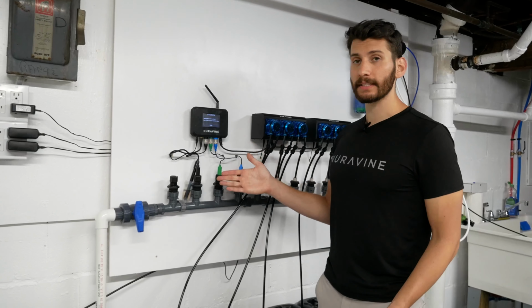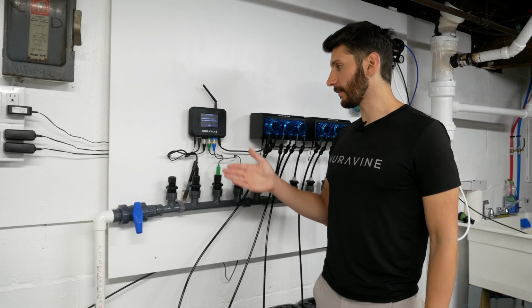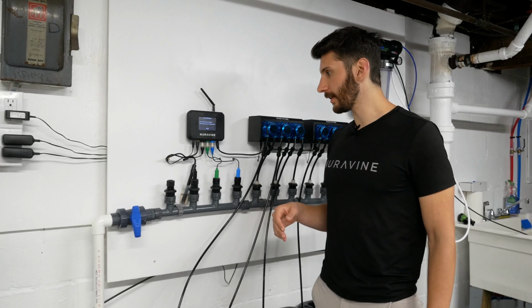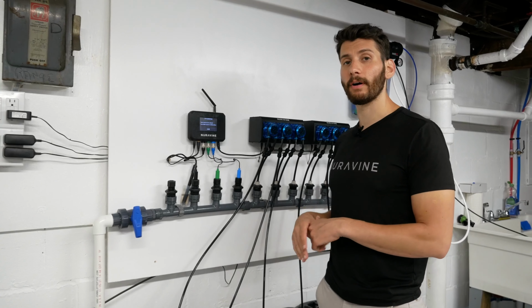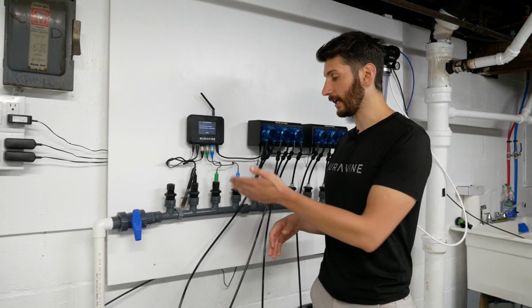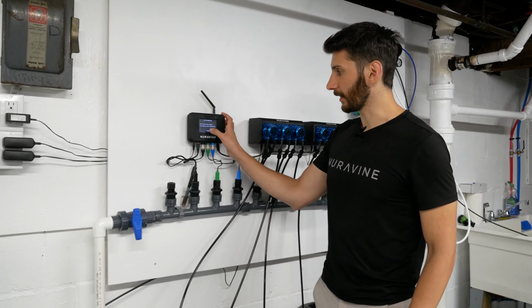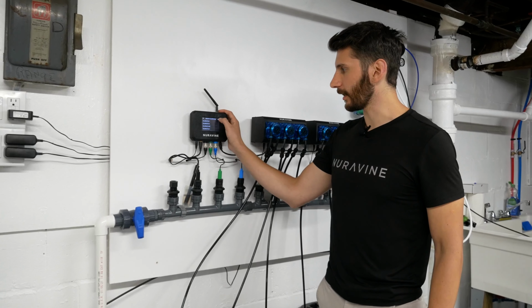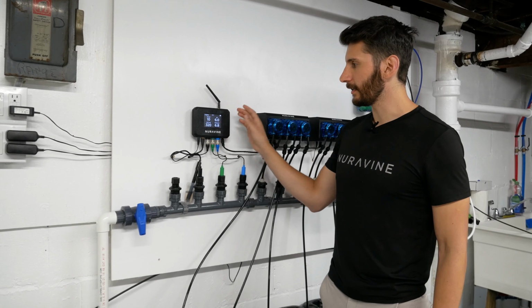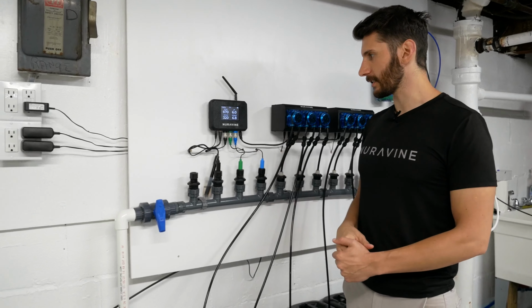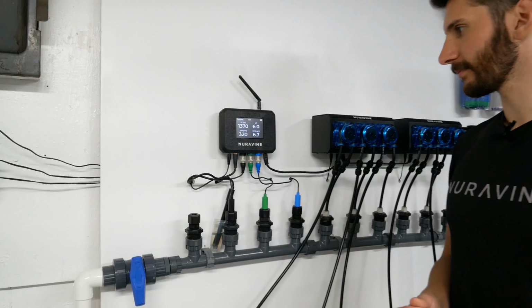So once that's done, you're going to see this confirmation screen saying the EC probe has been calibrated. And so what we're going to do is go over to the home screen and see if the reading is in fact what it should be. So we're going to click done, then click our little home button. And in a few seconds, you'll see that the EC is going to read a certain number.